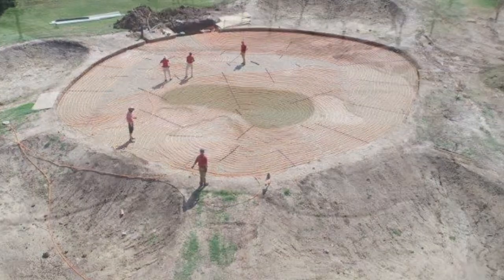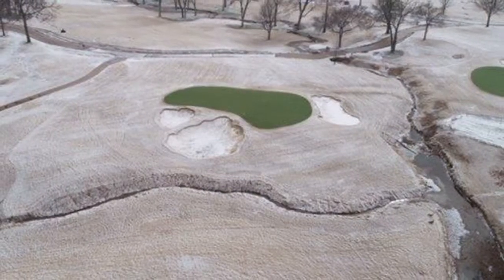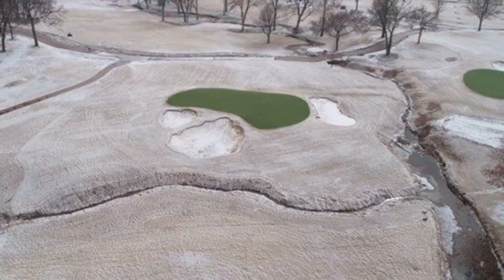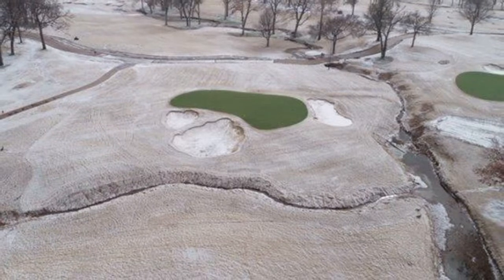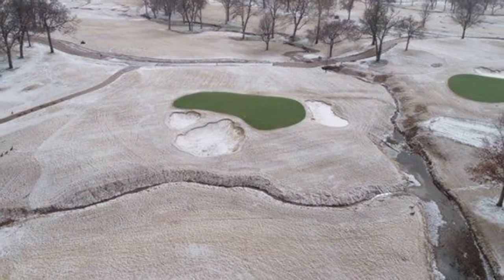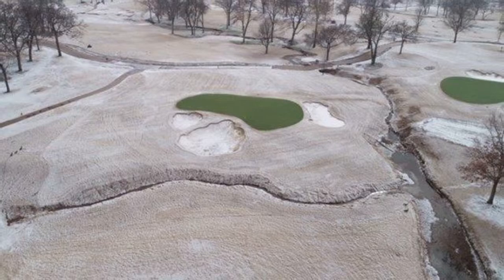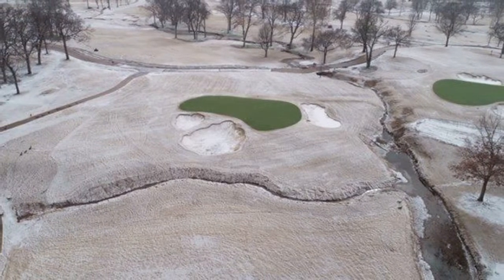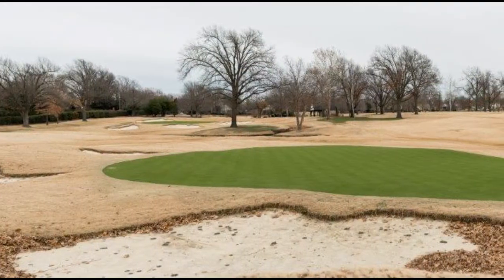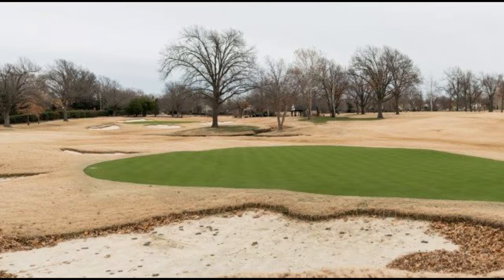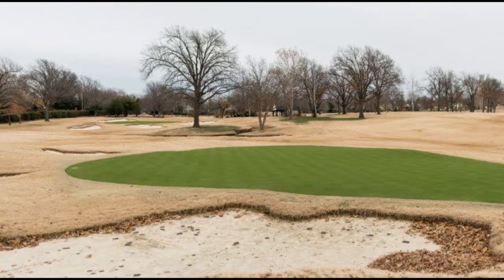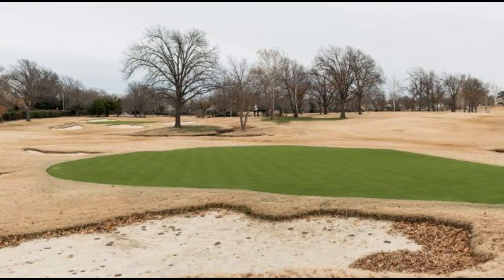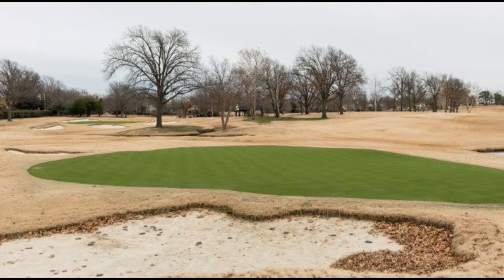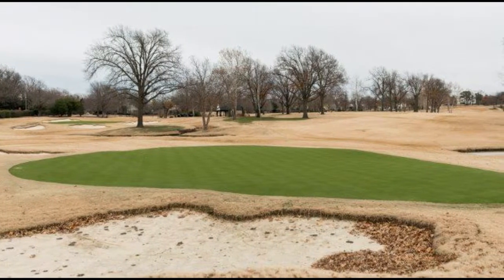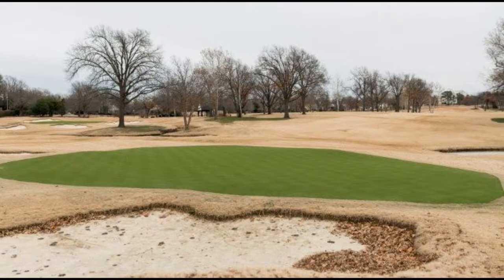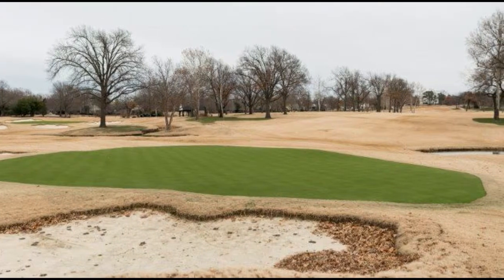Each started with 4-inch herringbone drains cut into the subgrade, or base soil, approximately 18 inches below the turf. 4 inches of pea gravel was laid over the base. Over that, radiant PERT tubing was laid at 9-inch centers. The final layer is a greens mix of sand and peat, and then the green was seeded with creeping bentgrass. The hydronic system installed at Southern Hills will pay dividends year-round. It's a major differentiating factor for Southern Hills as it allows for more play and higher quality services.